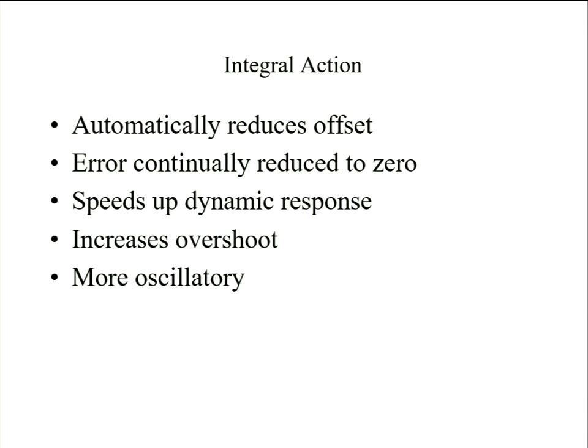But essentially, what a PI controller is, this is one version of it. What we've got is a set point, a measured variable, and an error going into the proportional term. But we've also got this thing here. What it's doing is integrating the error over time, so it's building that up. The error can be 0, and you can still have a non-zero value on the integral of error over time. So you can get a positive output with a 0 error. So it integrates the error out.